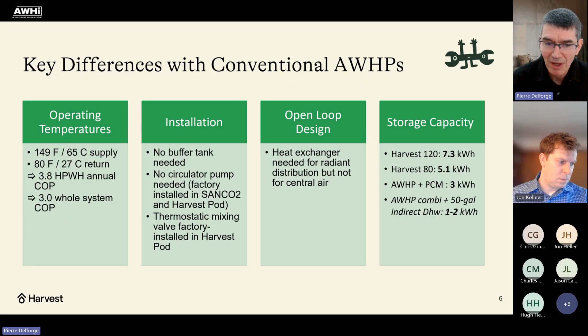Yeah, we use the storage tank as a big buffer tank, if you want. Think of the SANCO2 as a trickle charger in EV terms. It provides only a small portion of the direct heat. Most of the heat comes from the thermal battery. So you can meet up to 4 tons of heating load from the thermal battery, obviously only for a couple of hours. And that's why we need that auxiliary heat pump if you have a 3 or 4 ton load. Once the storage runs out, you're going to need to run the other heat pump while the SANCO2 recharges storage. But the instantaneous capacity of the system is around 4 tons maximum.